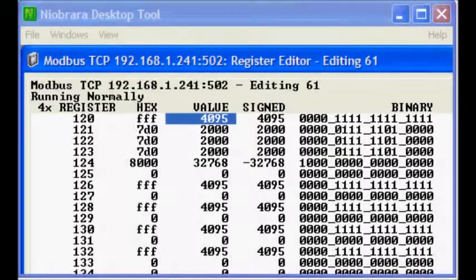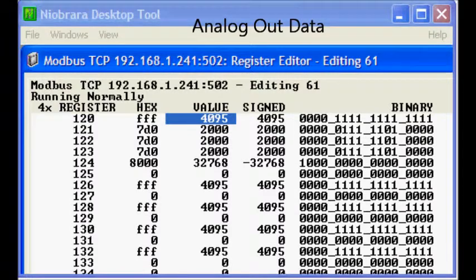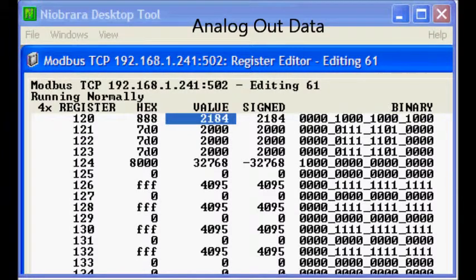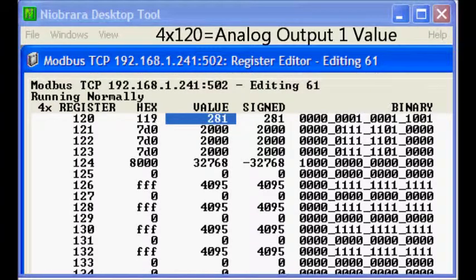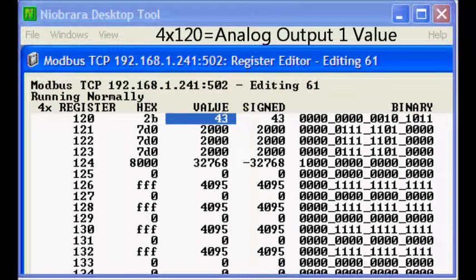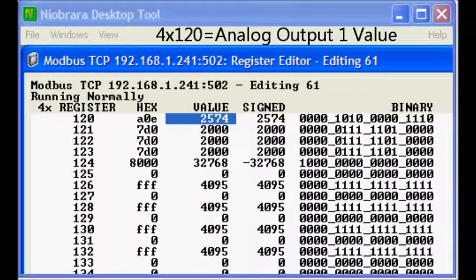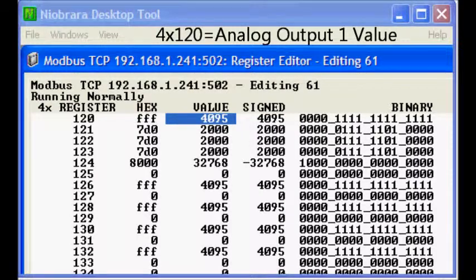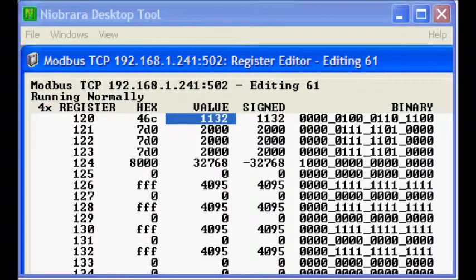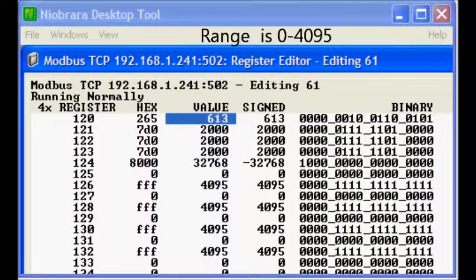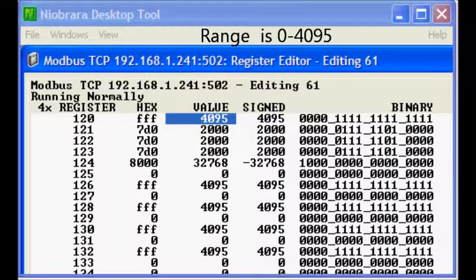The data transferred to the analog card starts at register 120. Register 120 is the actual analog output value. The value is limited to a range of 0 to 4095 and is being copied directly from analog input 1. As we turn the pot, the value changes through the possible range.